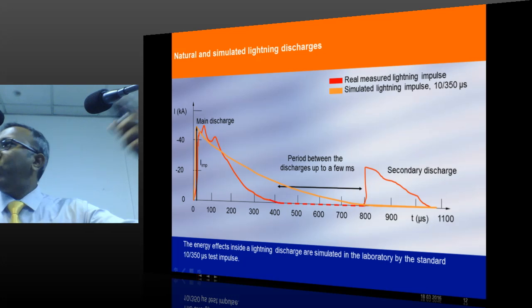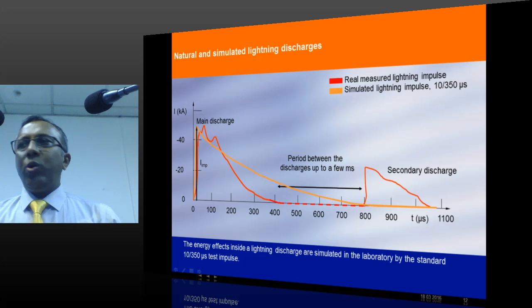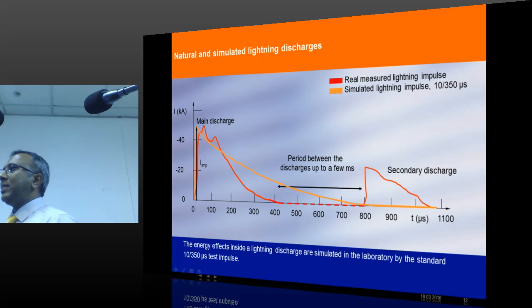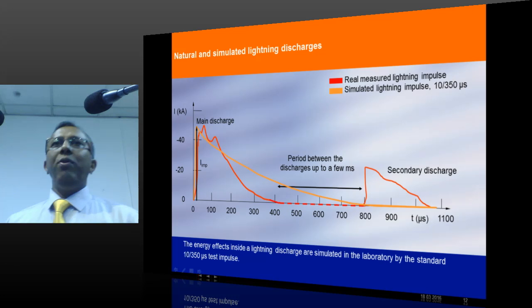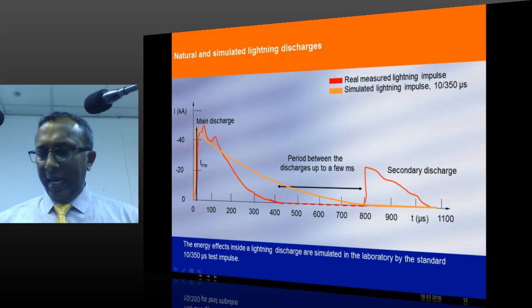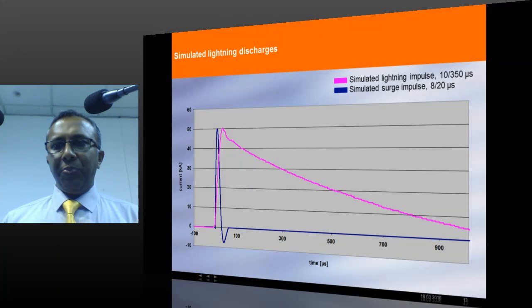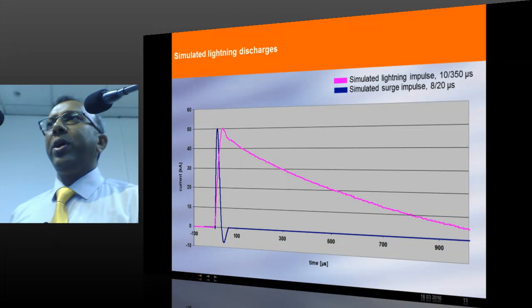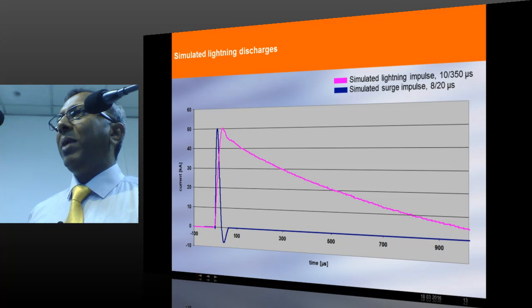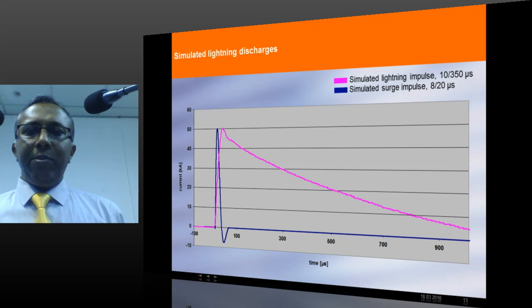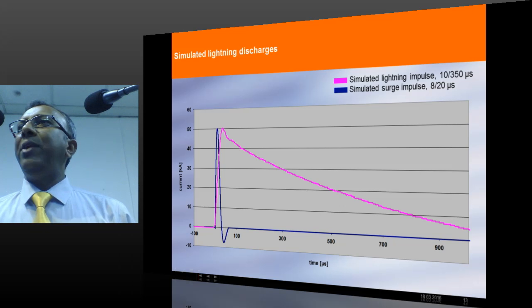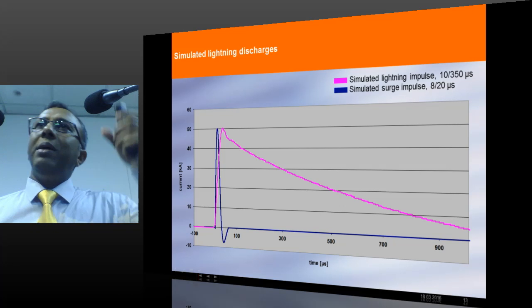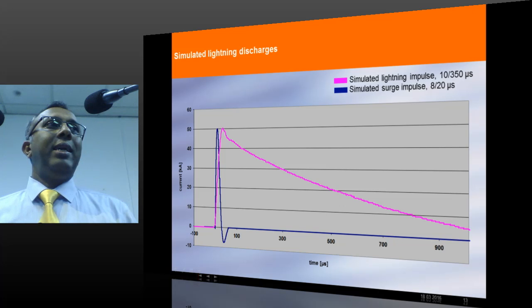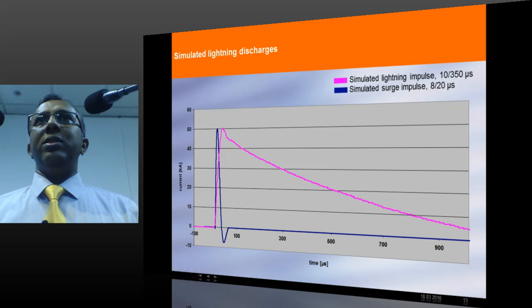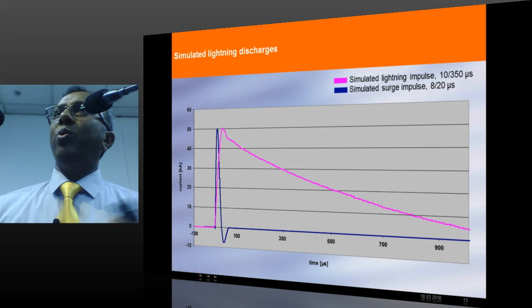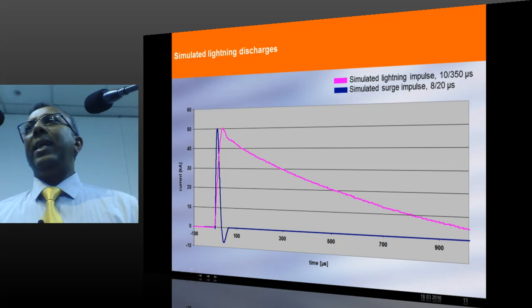Then we come to the current later on. So, there is a main discharge and there is a secondary discharge. Both are evaluated very well in the standard and the designing is done. Now, when we talk about lightning protection, we are talking about two wave shapes. One is 10 by 350. There is one more wave shape which is explained, called 8 by 20. The 8 by 20 wave shape is the energy equivalent of a transient surge, maybe a switching surge or a surge which is created due to coupling of a partial lightning current.